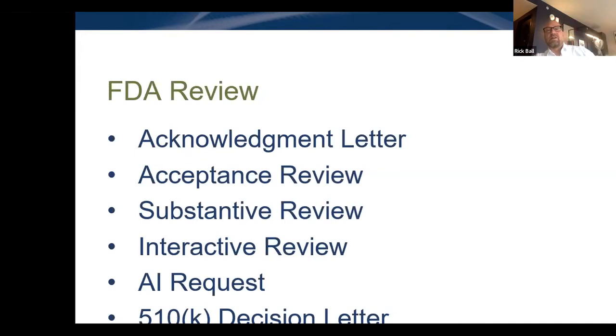So FDA will review it. They'll send you an acknowledgement letter. They'll accept it for review if you've got everything in it, and then they'll go through a substantive review. Now, the next two things are things where I know most manufacturers consider them a pain, but Sean asked me to talk about some things that actually might help you in future litigation. So if you have an interactive review with the FDA, or you have an additional information request, you can point back to that in the litigation, and say the FDA took a really deep look at what we were doing here. Here's the interactive review we had, the back and forth. Here's the additional information requests we had from them. And here's how we responded to those. And then eventually you'll get a 510K decision letter. Next slide, please.